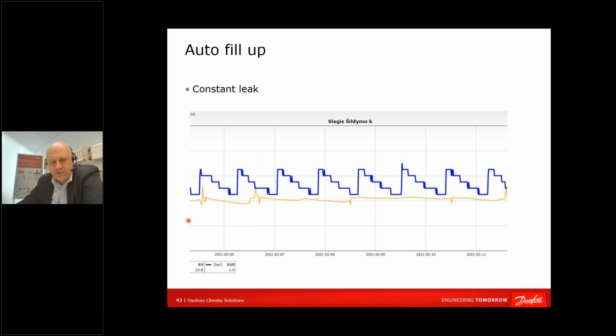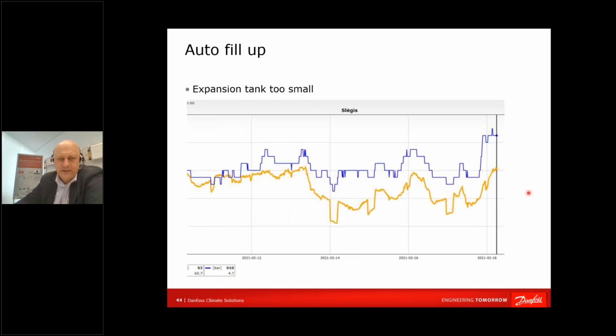How good is it for the customer, and what's good? A constant leak, from my colleague Robertas. Here you go. We are building up pressure, and pressure is decreasing. Then we see the temperature here, so something is wrong with that building. It constantly needs some feed water. Something should be done as a maintaining company. Your expansion tank is too little.